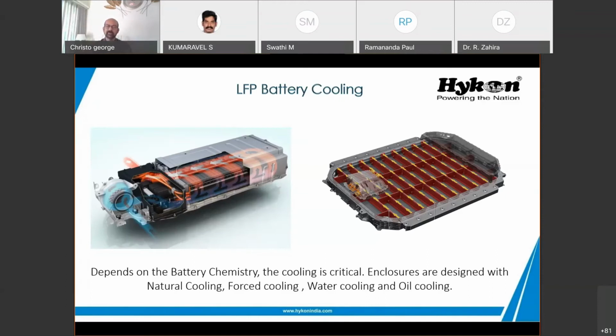So cooling becomes necessary. In some cases, like in an engine, you can see aluminum fins - a similar design has now been put into batteries, so there are fins and air flows through them to cool the cells inside. There are different types: in the left side picture, a blower is used to blow air through so it can suck air through and the hot air goes out. In another type, aluminum bars are kept inside the cells in that cavity, and the cells are assembled so that heat is taken out through the aluminum to outside the cabinet - the cabinet itself can also be made with aluminum.